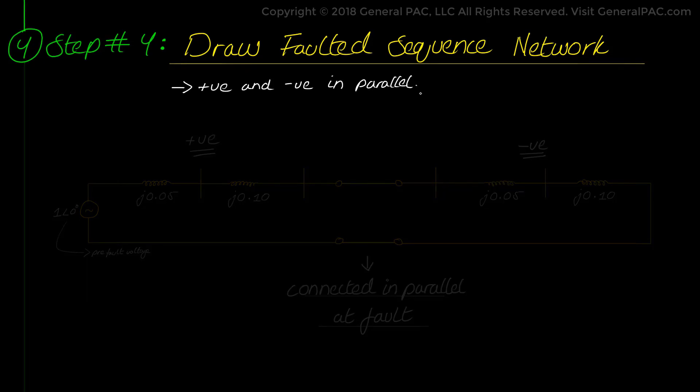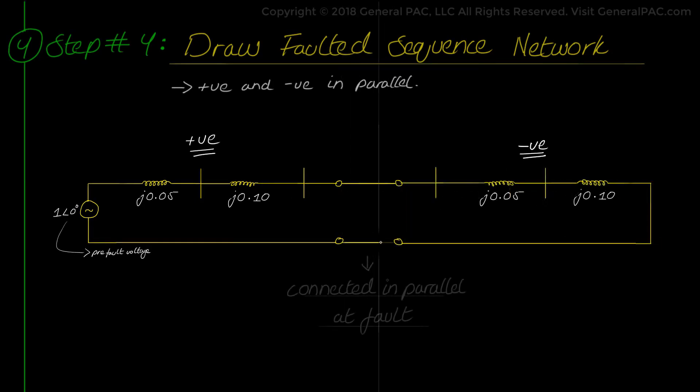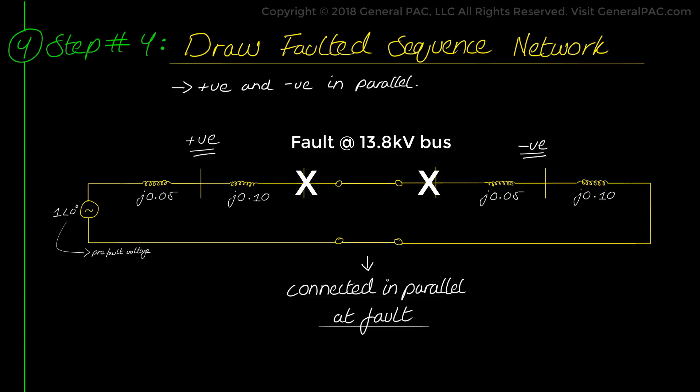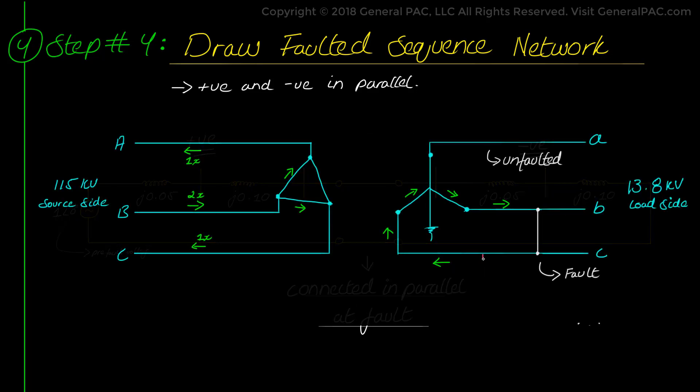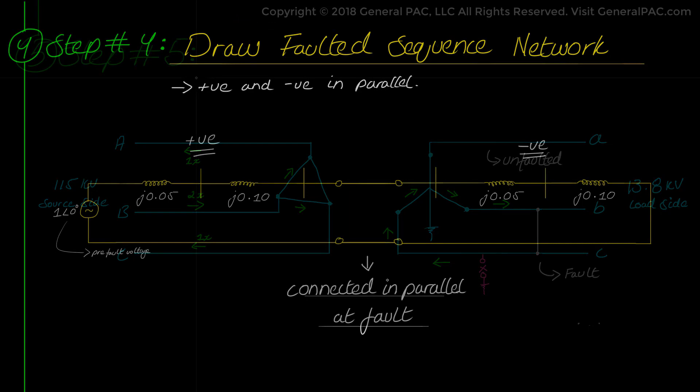To give a brief description of the faulted network, we basically have a positive sequence and negative sequence networks connected in parallel at the point of the fault. Line-to-line faults that are although unsymmetrical are not connected to ground which means that zero sequence current will not be able to flow from ground into the fault. And this explains why zero sequence networks are omitted from the construction of the faulted sequence network.